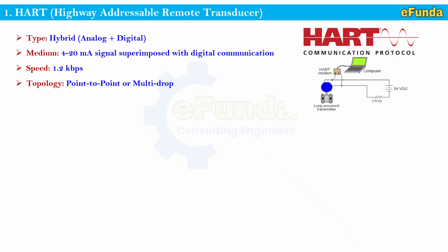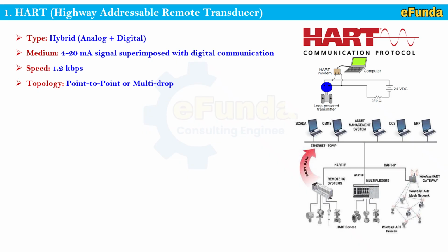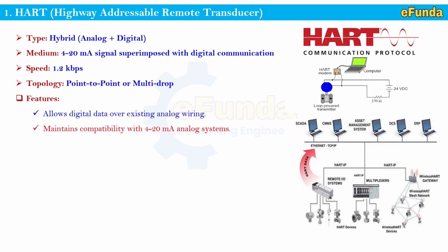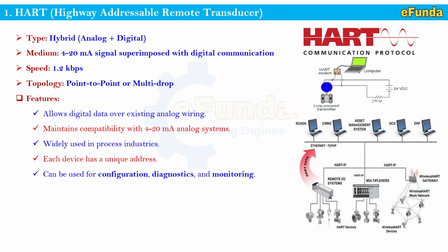One can refer to another picture where the field instruments are connected to the remote IOs, and then further connected through the Ethernet TCP/IP network to various systems called SCADA, CMMS, asset management, DCS, and ERP system. Here, HART is the communication protocol for field devices to connect with a control system, and the features are: it allows digital data over existing analog wiring, maintains compatibility with the 4 to 20 milliamp analog signal, and is widely used in process industries. Each device has a unique address and can be used for configuration, diagnostic, and monitoring purposes.